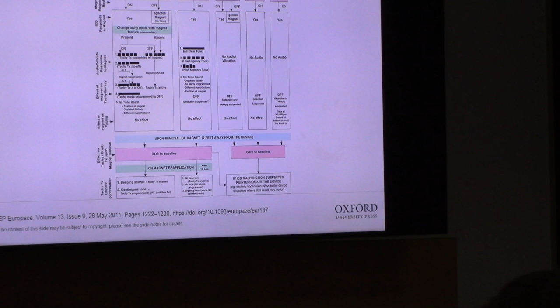What could happen potentially if you deliver a pacing spike where it's not supposed to go? Yeah, so what might happen? The patient can potentially have VTAC. So if you identify that, when you have the magnet placed and you see them going fast on the EKG, because the magnet is only going to pace at a particular rate, you will be monitoring the EKG to take the magnet off. Don't allow it to pace so you don't get into a potential situation like that. So that is why magnet use might be better than even reprogramming in most cases. Right?